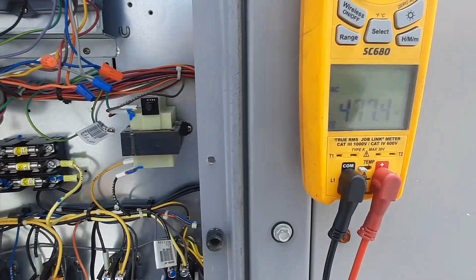And let's take a look at the diagram and see what it feeds. Let's verify I've lost my power. Alright, so I got no voltage. Overload wasn't tripped here. I believe that's for the blower. And everything else is going to be okay once we get power to that transformer. I bet we have 24 volts and everything works. But we got to find out something on the high voltage side tripped that fuse or fuses.